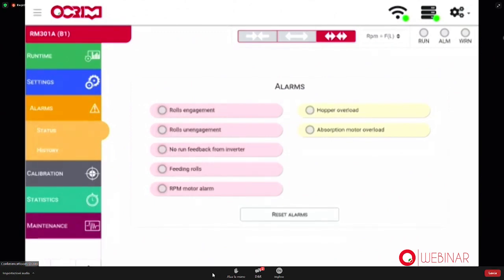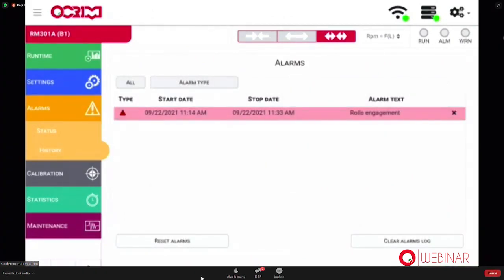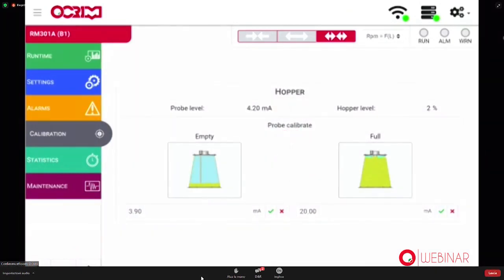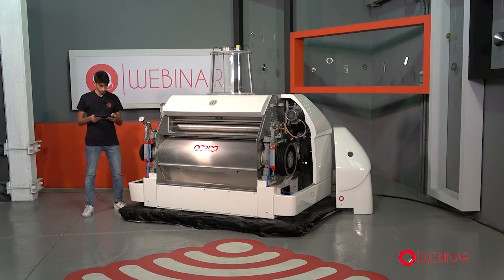In this page, you can see the state of all the different alarms. In this case, no alarm is active, but if we had an alarm going on, you could see the LED on, and then there's also a reset alarm button. Then the second part of this page is a register of the events where you can record all the primary and secondary events that occurred within the machine. Then we have a calibration page. In this version, we only have level calibration. In this page, we associate the 4-20 milliampere signal to a percentage value from 0 to 100.